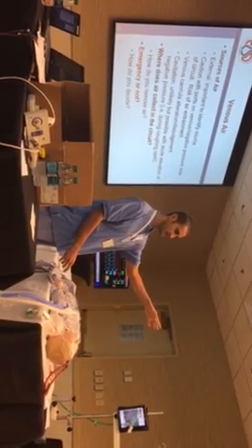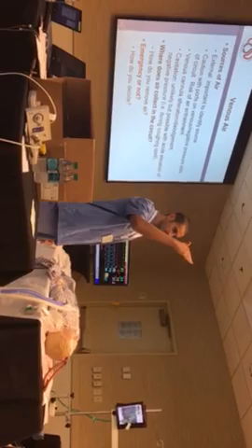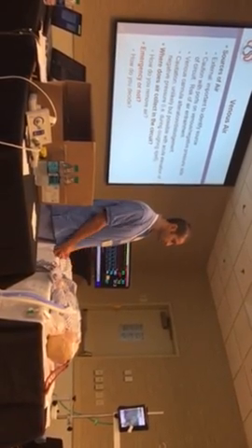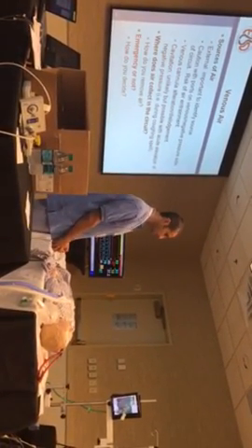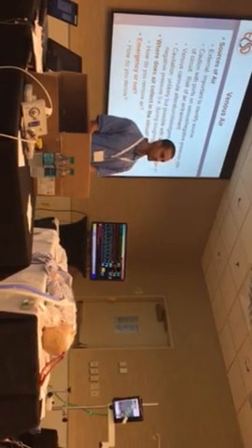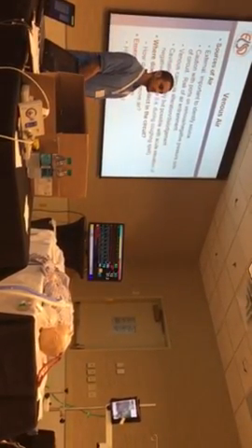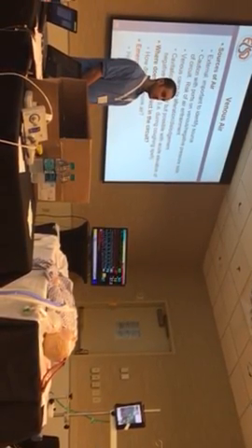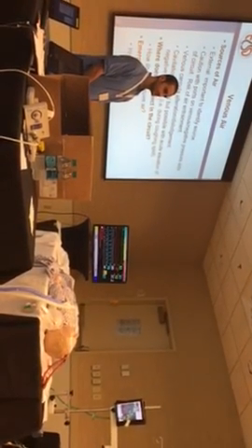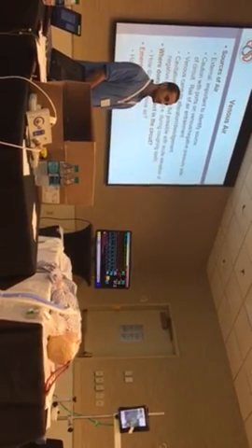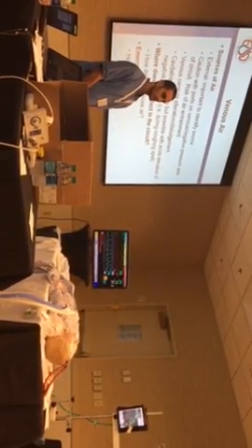And you guys did see some effect of that, right? Yeah, huge. Your flow went from normal to pretty dramatically dropped. And then the next sink, of course, is the oxygenator, as we said. So with the Cardiohelp, since it's integrated, is it arranged so that it goes straight up?